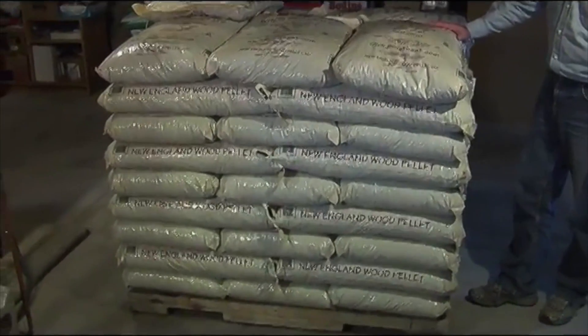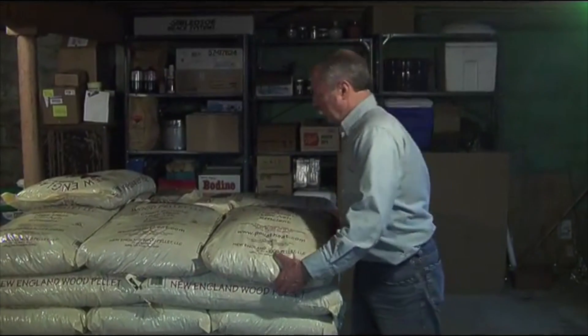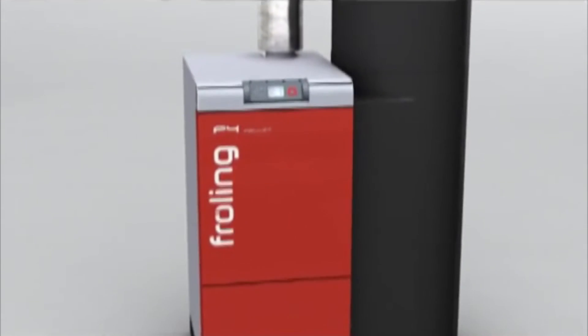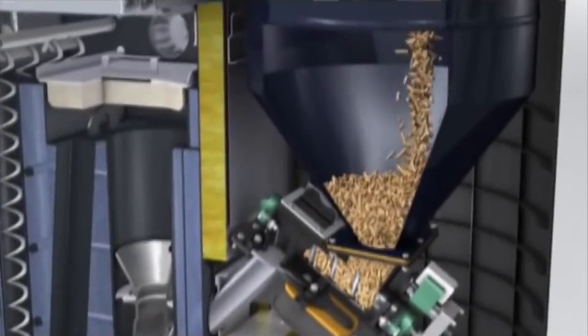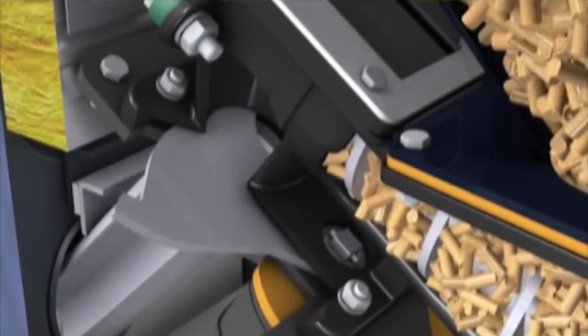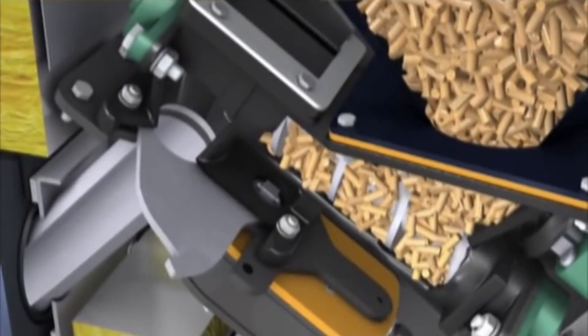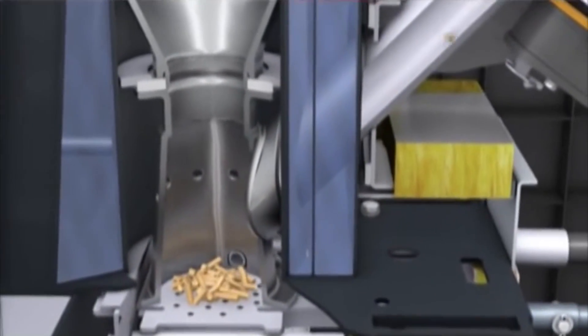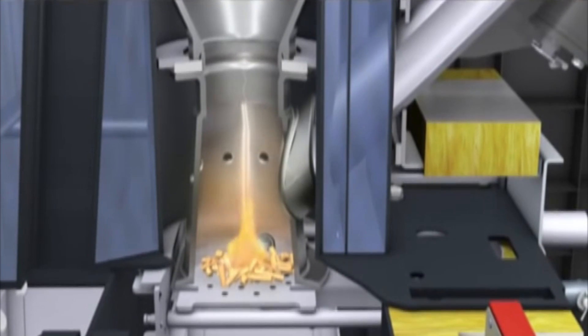Wood pellets seem pretty great — they're a natural waste product with a slim fraction of the carbon emissions that come from fossil fuels. Let's take a closer look at how we actually translate these pellets into energy for your home. Here is our system: a Froling P4 wood pellet boiler. It operates fully automatically, from cleanup to ignition to pellet delivery. The pellets are suctioned from the storage unit into a supply bin, then dropped piece by piece into a drop tube onto a steel combustion chamber. With a steady stream of hot air, the pellets are controllably and automatically ignited to provide efficient heat production. The heat then rises and is carried through a series of distribution pipes to be brought to the rest of the home.